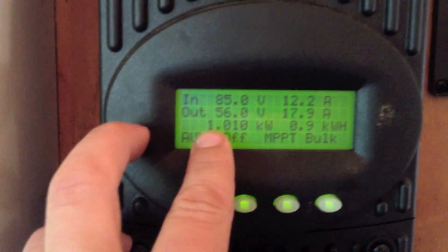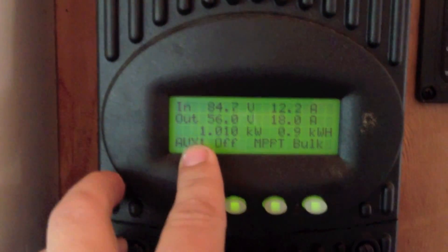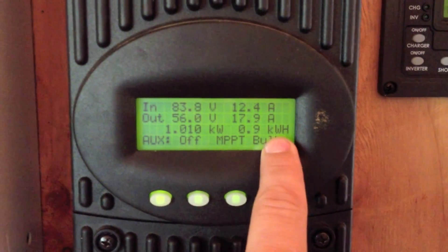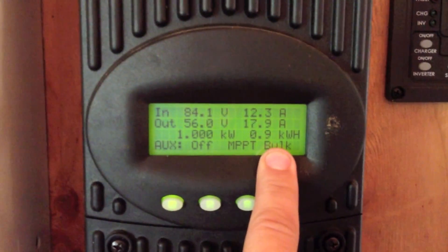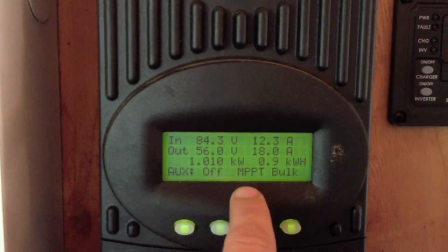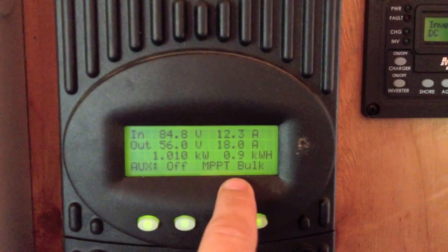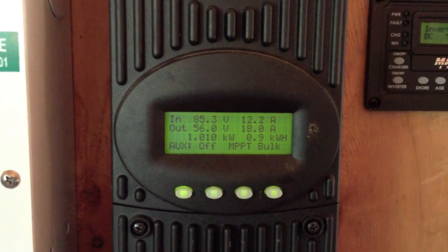We have this next reading below — that's the solar production of the panels at the exact moment. The sun is just rising right now; it's 9:30 in the morning. This is kilowatt hours — the cumulative amount of energy collected in the day. Auxiliary mode is options we're not using — they're off. This is saying that maximum power point tracking is on. It's in bulk charge mode, charging the batteries from everything used last night.